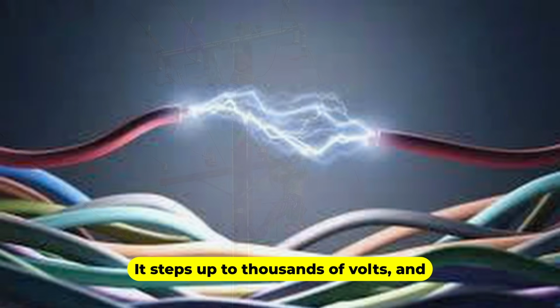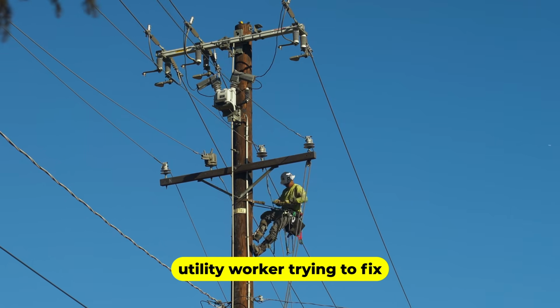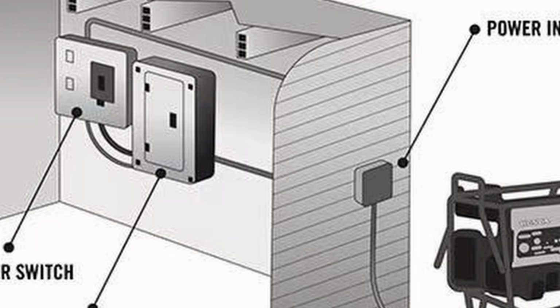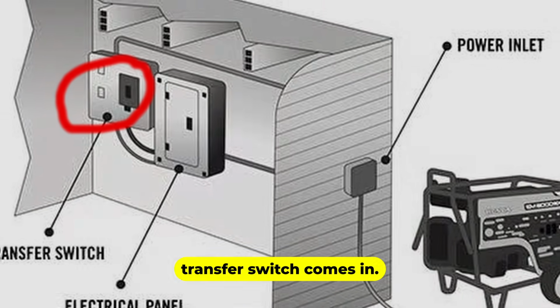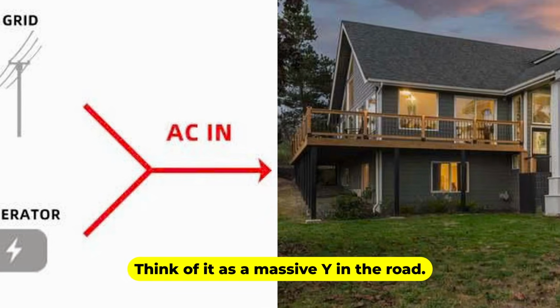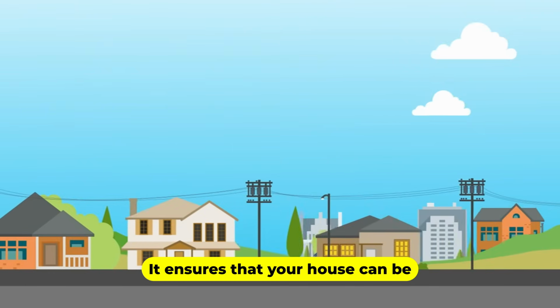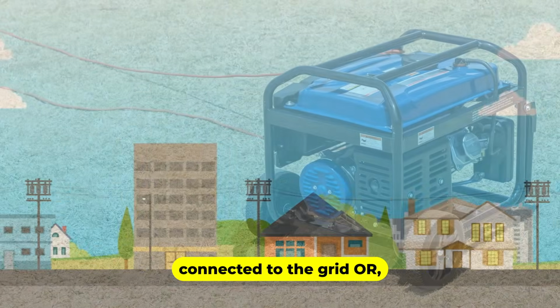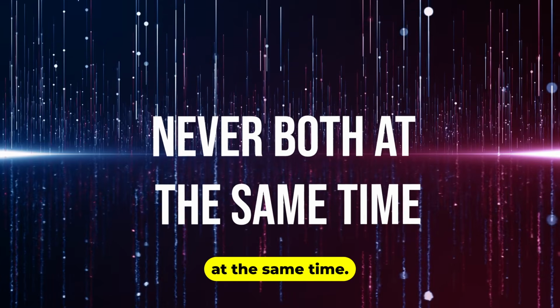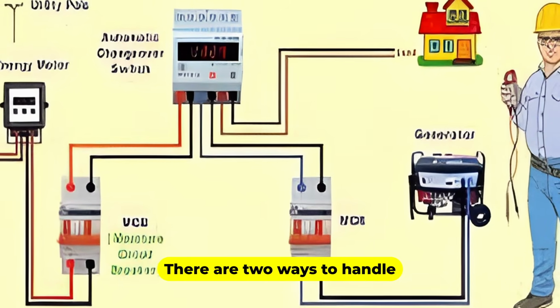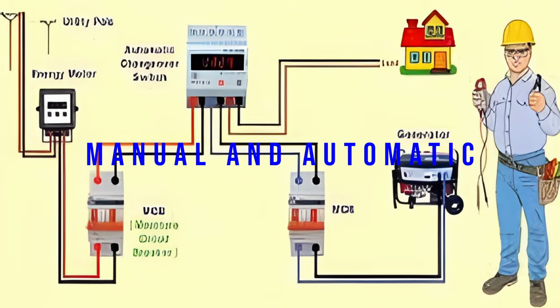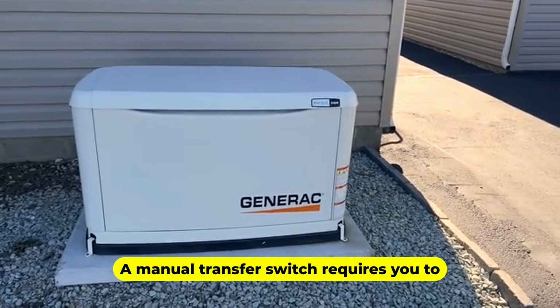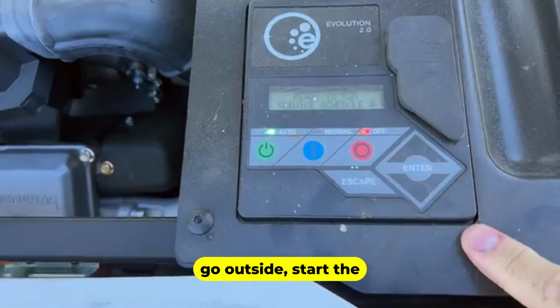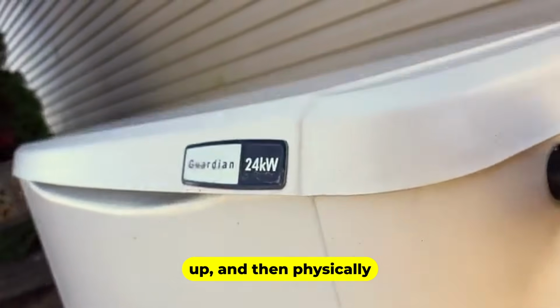It steps up to thousands of volts and can easily kill a utility worker trying to fix the lines. This is where the transfer switch comes in. Think of it as a massive Y in the road. It ensures that your house can be connected to the grid OR the generator, but never both at the same time. There are 2 ways to handle this: manual and automatic. A manual transfer switch requires you to go outside, start the generator, let it warm up, and then physically throw a heavy-duty lever. It's simple, it's reliable, and it's significantly cheaper.